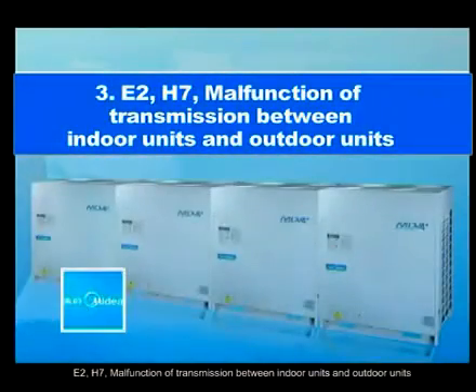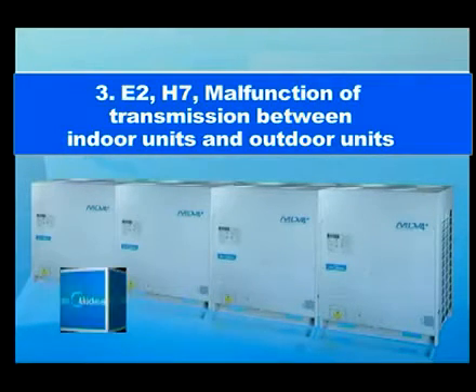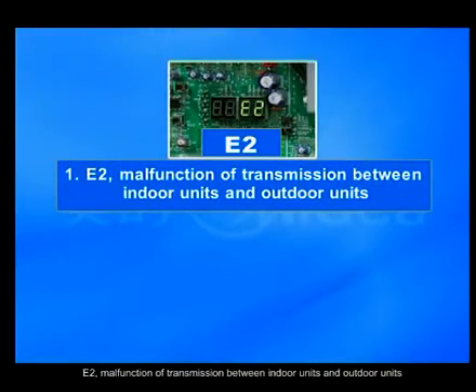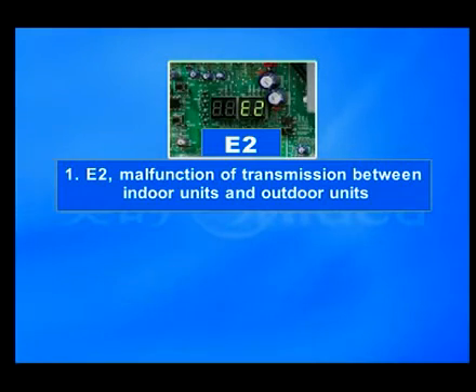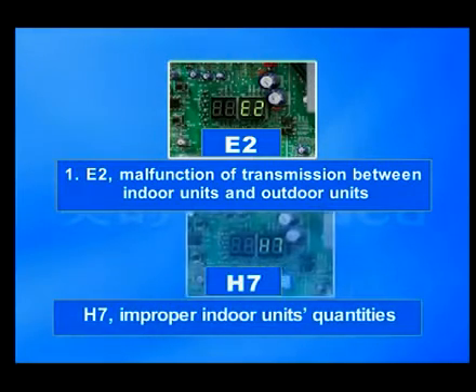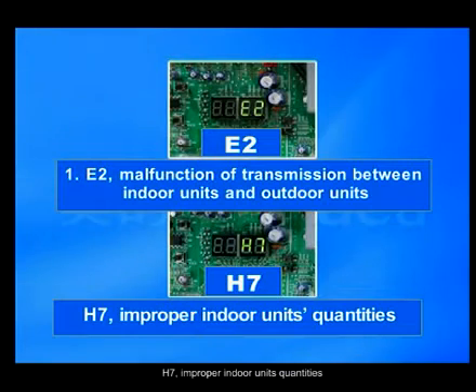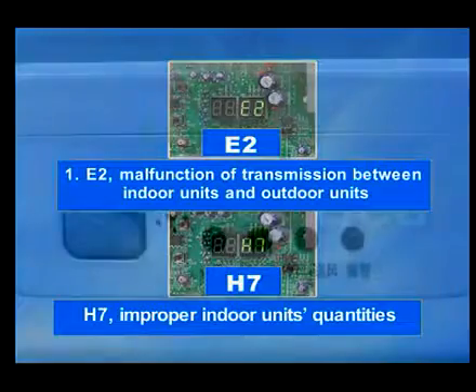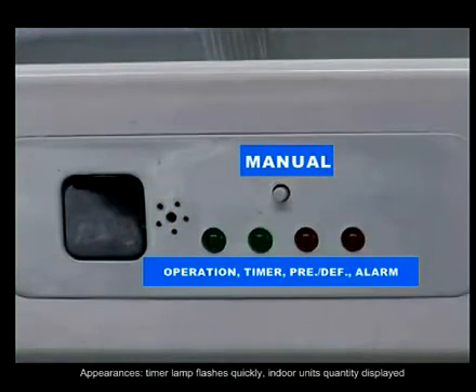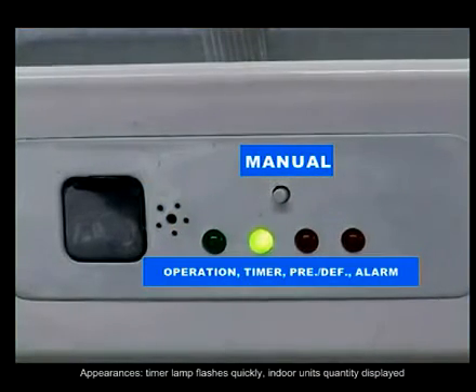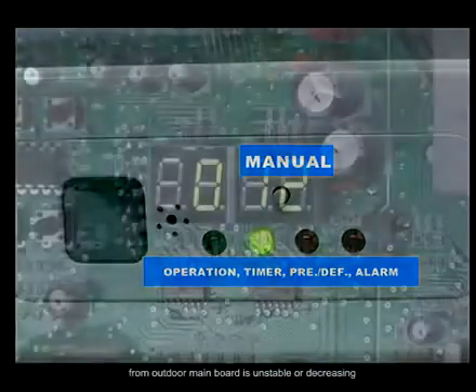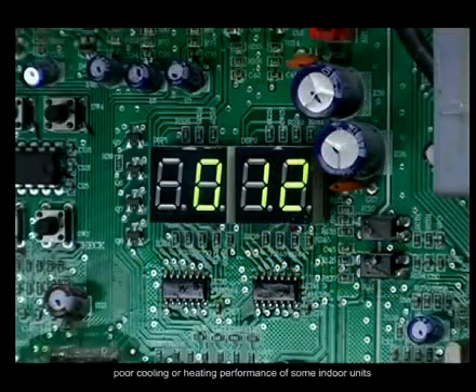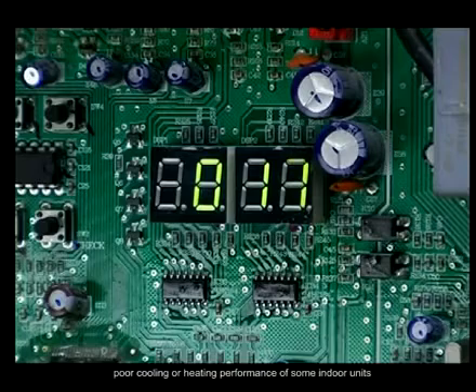E2, H7 malfunction of transmission between indoor units and outdoor units. E2 malfunction of transmission between indoor units and outdoor units. H7 improper indoor units quantities. Appearances. Timer lamp flashes quickly. Indoor units quantity display from outdoor mainboard is unstable or decreasing. Poor cooling or heating performance of some indoor units.